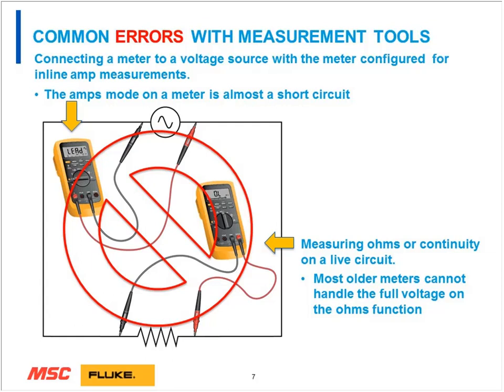So amps mode on the meter is almost a short circuit. Also, measuring ohms or continuity on a live circuit, a lot of older meters can't do that. Now, Fluke meters are designed with a protection circuit that's built into the instrument to extinguish any type of arc, where you can measure up to 1,000 volts in any switch position and nothing bad will happen. Not all meters are built that way, but I can speak to Fluke. Older meters, even though you may have an older meter, and we'll talk a little bit about this, may not be designed for the amount of currents that we're measuring today with the higher amperage circuits.